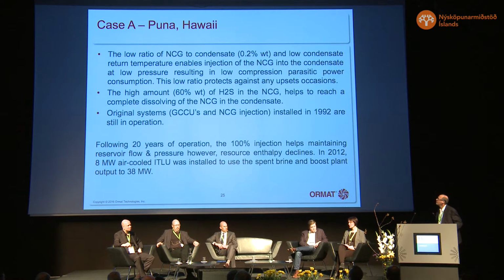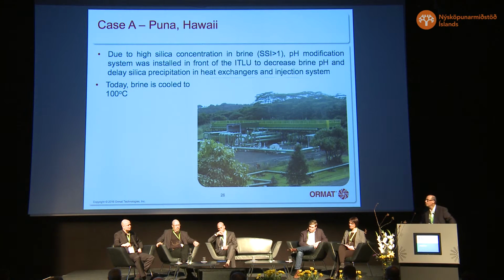Just to emphasize, the original system, the generating unit equipment and the NCG equipment, are still operating since 1992. After 20 years of operation, there was some decline in enthalpy, but not in flow, mainly in enthalpy. In order to boost again the power of the power plant, in 2012 an integrated 2-level unit of 8 megawatt, which utilized the brine only, was installed to increase the power to 38 megawatt. Due to the high silica in the brine, we have a pH modification system in front of the system, which enables us to delay the silica precipitation in the heat exchanger and in the reinjection lines.